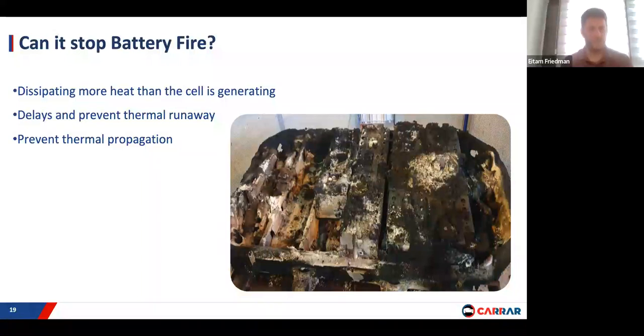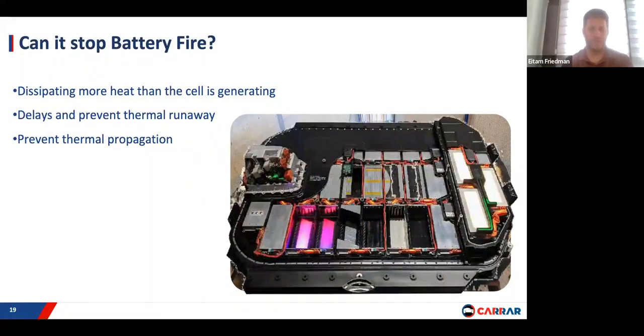Yeah, so I can disclose a bit that we have performed a test on thermal runaway, a very aggressive test. We managed to hold thermal propagation for 50 whole minutes on high energy cells. A very smart professor from NREL once told me that if you dissipate more heat than the cell is generating, you will prevent thermal runaway. As you learned in the previous slide, Carrar's capability to dissipate the amount of heat generated by a cell or a group of cells means our system can take care of this heat. So we won't reach the point of runaway or propagation. The potential to prevent thermal runaway, and also thermal propagation, is enormous.